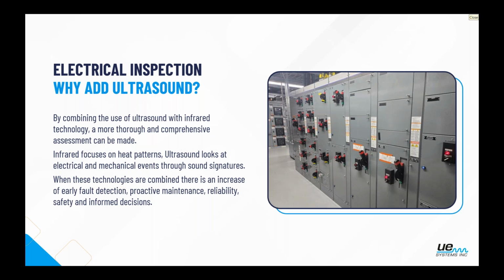The other point too, beyond making sure that we are finding everything that we're looking for and not having to re-inspect multiple times, is that it really makes it safer. I'm sure everyone's seen it, MCC rooms where there's a whole bunch of medium and high voltage equipment, and unfortunately not everything has an infrared window in it by standard design. So what that means is a lot of the stuff has to be open to have a proper inspection. And just like with ultrasound, we need that equipment to be energized to perform a proper inspection. Personally, I would like to know that regardless of what PPE I'm wearing, if I'm about to have a very bad day opening up that cabinet to do an inspection.